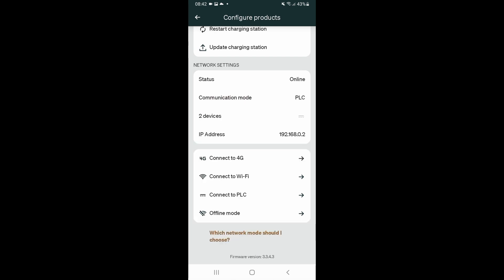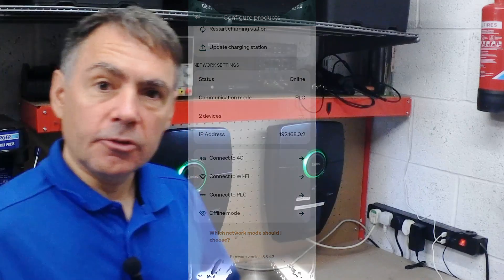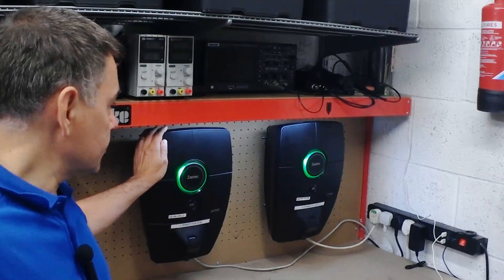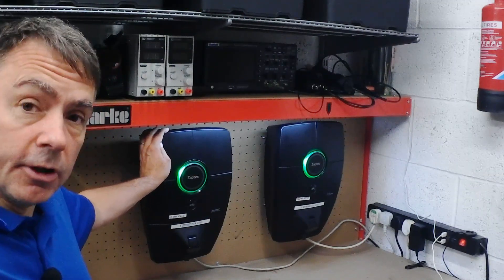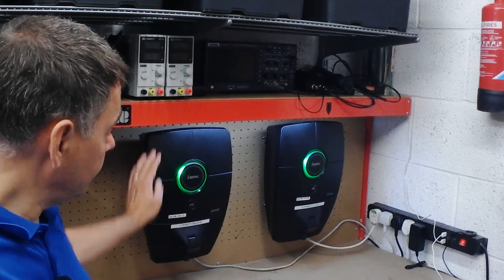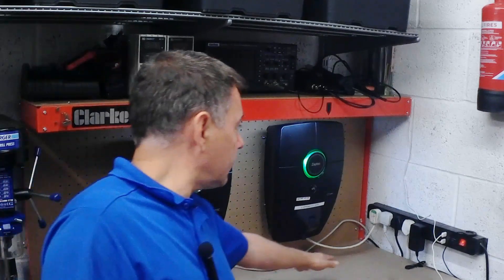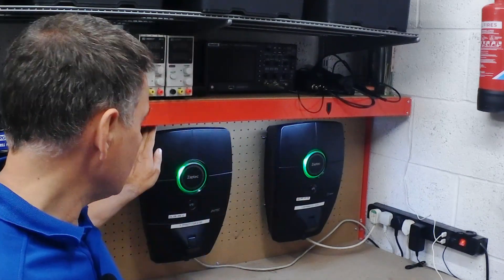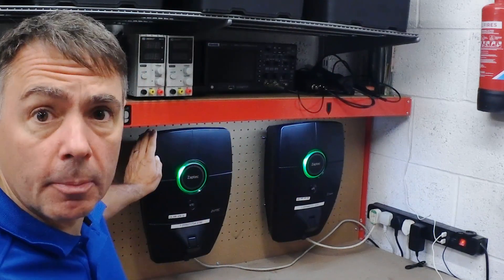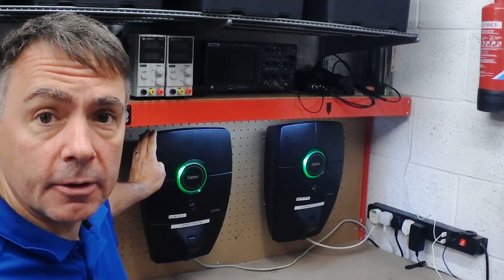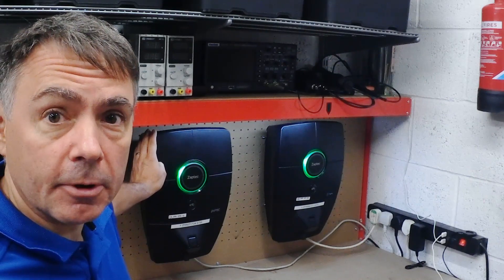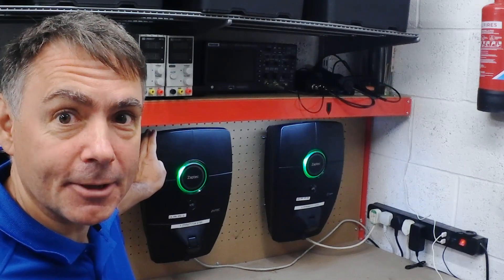There we go. Charger is now online. It's got an IP address connected over powerline carrier. So now this charger has a good network connection. It's not using radio. It's using powerline carrier to connect to this charger. So we've solved the problem. This charger is now online with a reliable network connection. Job done. Thank you.